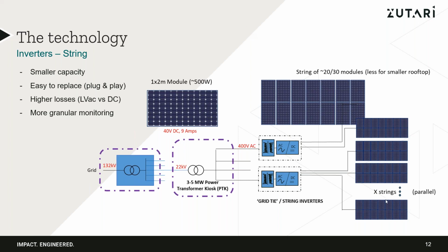So with those string inverters, we get your DC direct into the string inverters, and LVAC on the outside, typically 400 to 800 volts. Those will then run in trenches through to a power transformer kiosk, and you'd have your MV transformer in there, which is generally an 800 V to 22 or 33 kV transformer. Then you'll have your medium voltage out to your grid connection substation, and then it's generally 132 kV or below or above that out from that side.